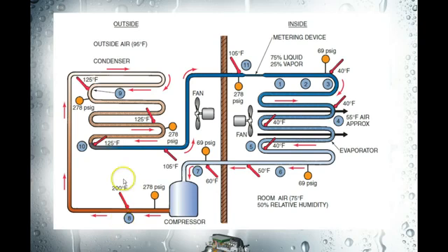So we continue to come down the condenser coil, and at a certain point we have now a solid column of liquid, and we have exited the saturation temperature and dropped off of our pressure temperature chart, and this is just a solid column of liquid refrigerant. And now any heat removed is sensible heat, and that's called subcooling.